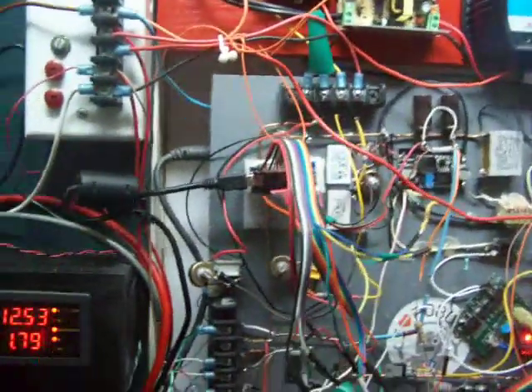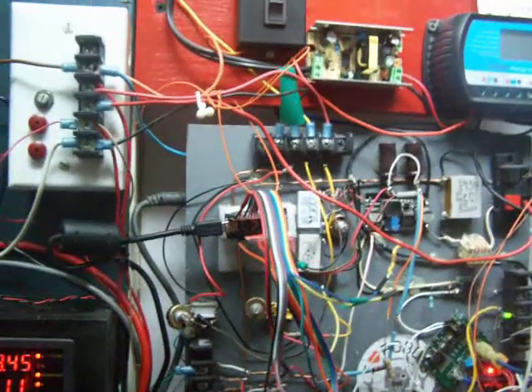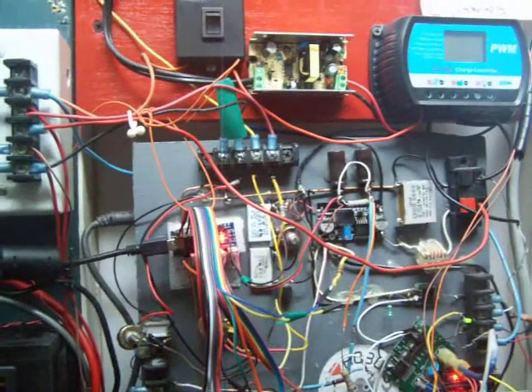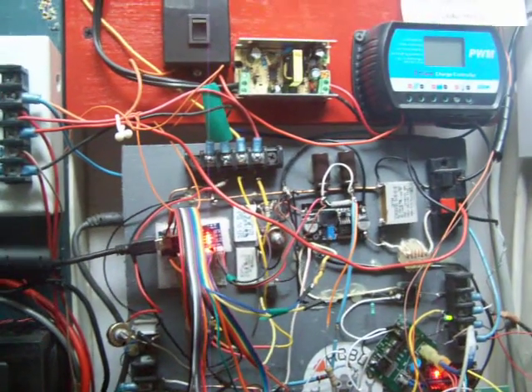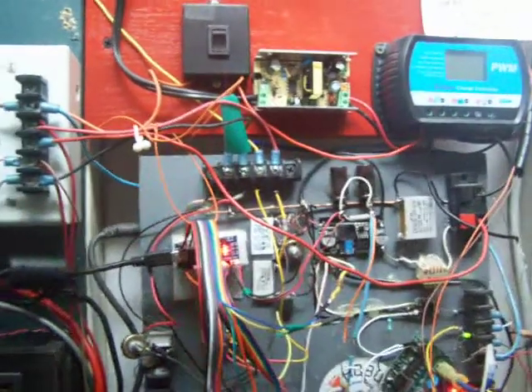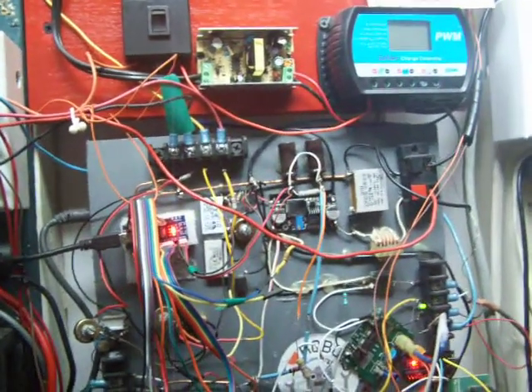These cables are really cheap - they have about three strands of wire on them. Basically each cable is about two cents each, and you get what you pay for. Trouble is you can't really specify buying a better one unless you're getting it from a really expensive source. The refrigerator came out of digital output 4, and there was just no connection. I've seen this before - every once in a while you get one of these with no connection. Luckily I had a spare port and I moved it over to digital 6, and then everything worked again.